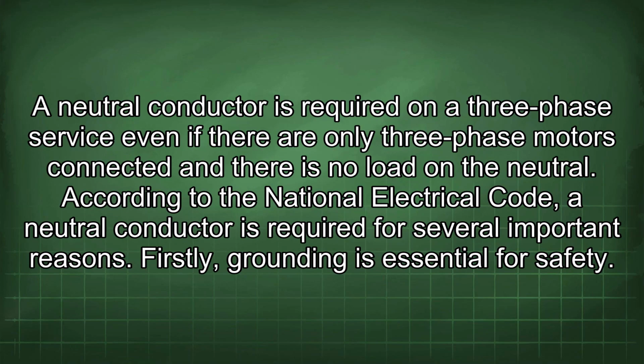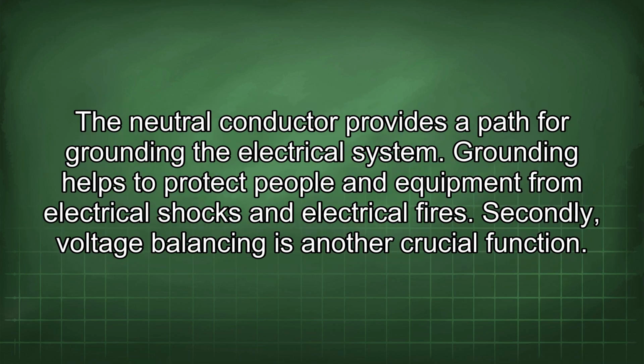A neutral conductor is required on a three-phase service even if there are only three-phase motors connected and there is no load in the neutral. According to the National Electrical Code, a neutral conductor is required for several important reasons. Firstly, grounding is essential for safety. The neutral conductor provides a path for grounding the electrical system. Grounding helps to protect people and equipment from electrical shocks and electrical fires.